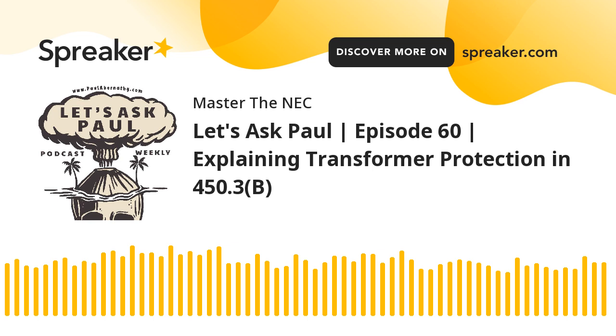Now, we don't know the conductor size yet, but we know that when it comes to the ampacity value, it can safely terminate into an overcurrent device at 175 amps. Okay, that's the device. We're taking it secondary. Since it doesn't correspond to 156, we have to use the next size up, which is 175 amperes. Now remember, we're not upsizing the conductors. We're selecting the device that they're going to terminate into. We haven't picked a conductor yet. We're just sizing the overcurrent protection.